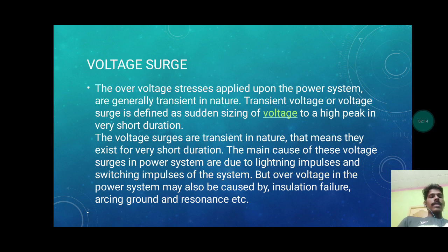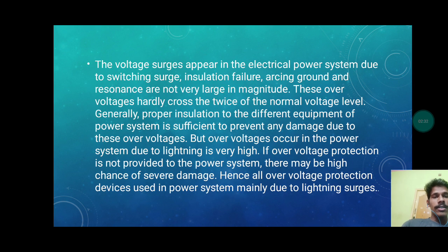The main causes of these voltage surges in power systems are lightning impulses and the switching impulses of the systems, but over voltages in the power systems may also be caused by insulation failure, arcing ground, resonance, etc. The voltage surges appear in the electrical power systems due to switching surge. Insulation failures, arcing grounds and resonance are not very large in magnitude.